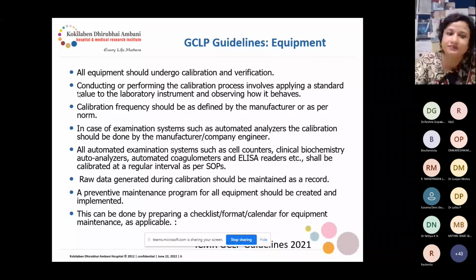And the preventive maintenance program for all equipment should be created and implemented, and this can be done by preparing a checklist format and calendar for the equipment maintenance as applicable. If there is a checklist or a calendar, we know when the PM is due. You can keep it on display on the instrument, that PM is due maybe June 26 or something like that. Then whoever is working in that lab, even the junior-most technical officer, knows when the PM is due for that instrument.